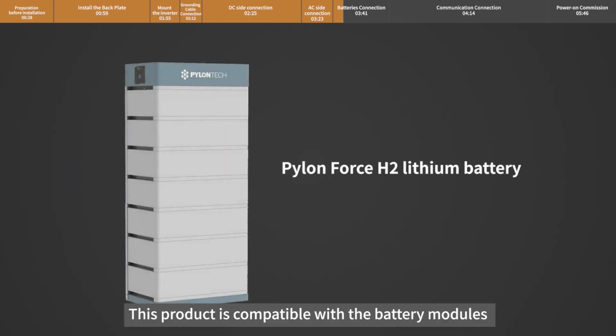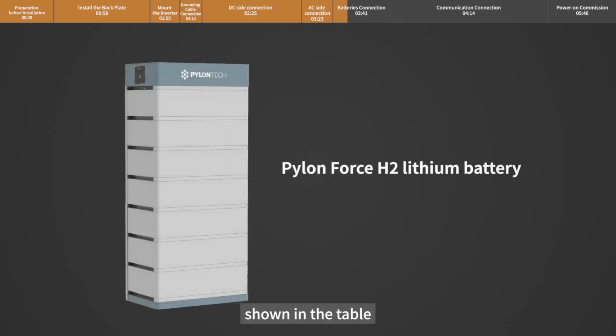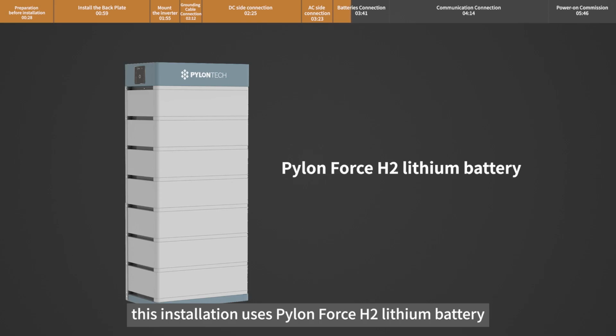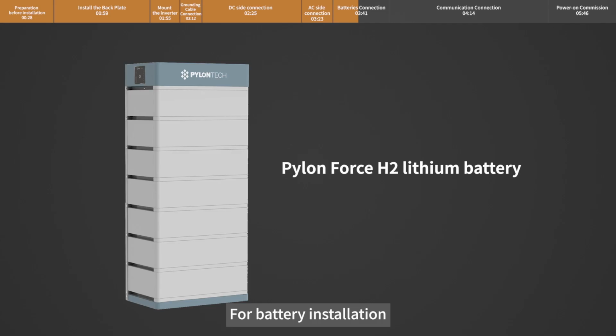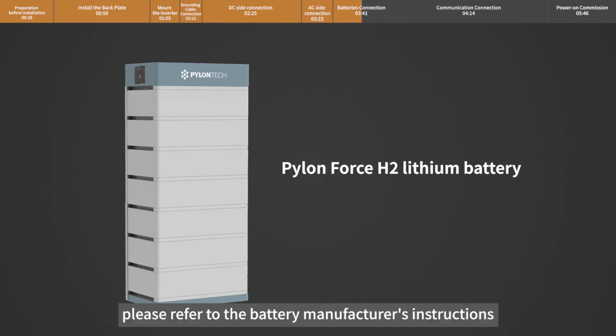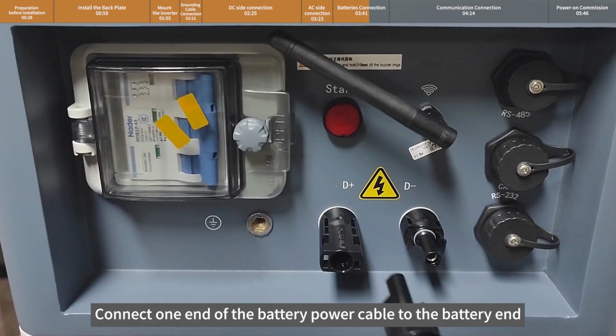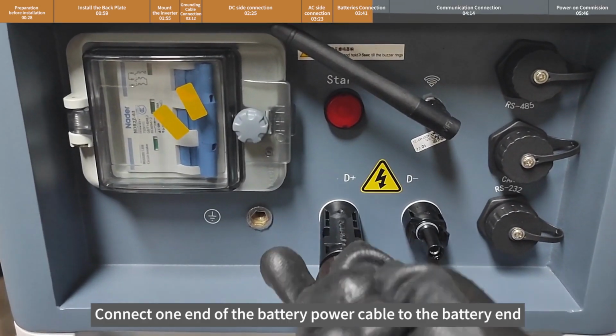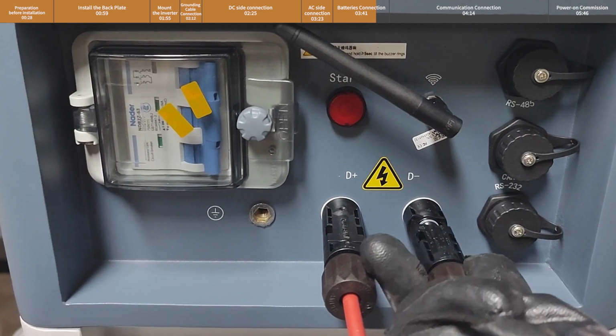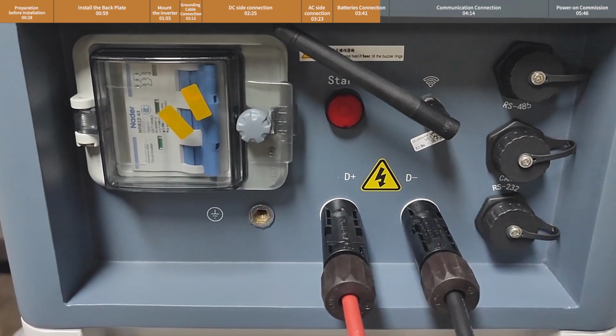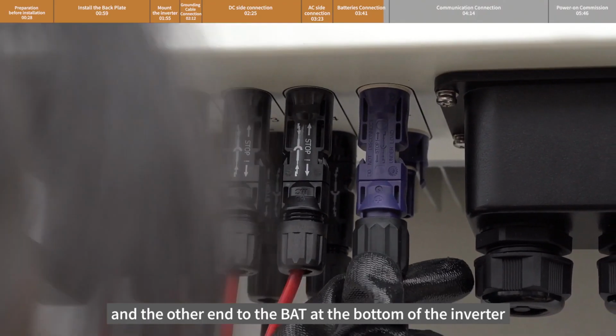This product is compatible with the battery modules shown in the table. This installation uses the Pylontech Force H2 lithium battery. For battery installation, please refer to the battery manufacturer's instructions. Connect one end of the battery power cable to the battery end, and the other end to the BAT port at the bottom of the inverter.